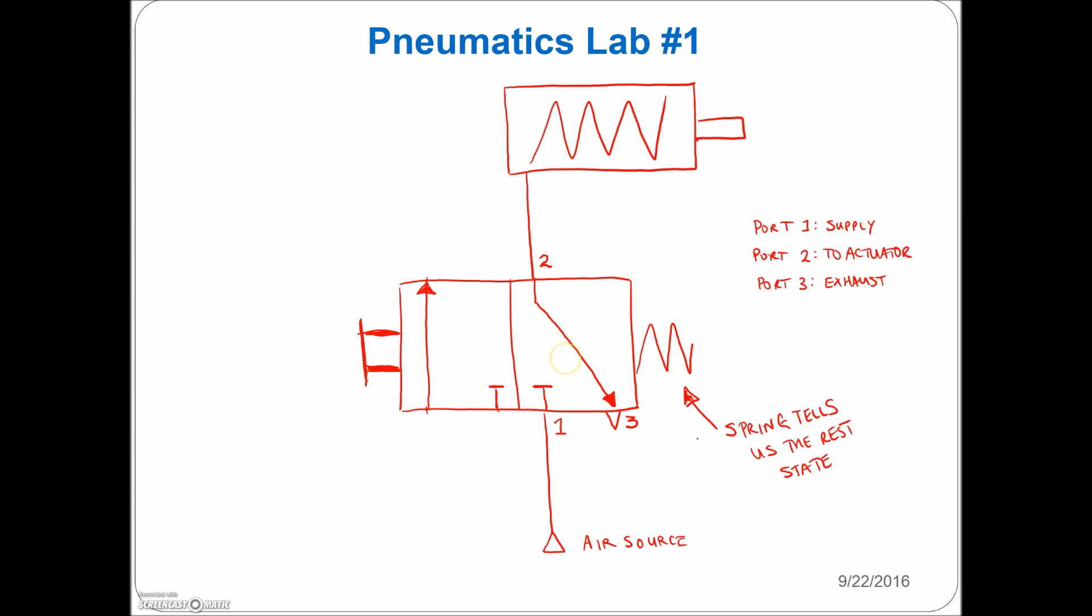Okay, this switch that we're using is called a 3-2, manually operated, push button actuated valve. What does the 3 and the 2 denote? The 3 denotes the number of ports. The 2 denotes the number of positions of the switch.